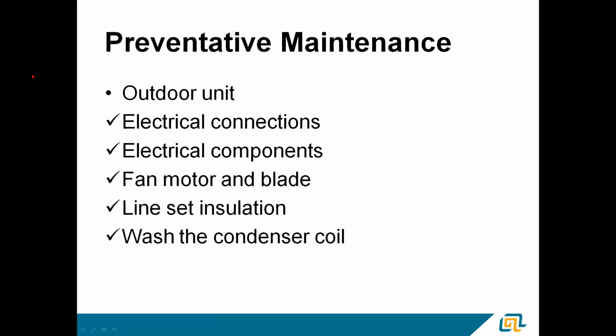The outdoor unit, again, check those electrical connections, make sure there's good integrity. A lot of mouse damage out there over the last few years. I don't know what that's all about, but I've seen a lot of rodents chew up a lot of air conditioners and heat pumps. So that's something to keep an eye on. Check the electrical components, the start components, the run capacitor, the contactor. Make sure they're all in good shape, that there are no spider webs in the contactors or anything like that. Fan motors and blades, and I think this is extremely important with a heat pump. Make sure that if the unit's been running through the winter, there was no damage from ice or snow or anything building up on that blade. Take a good look at it, make sure it's in serviceable condition.